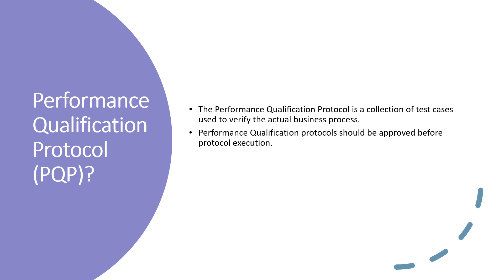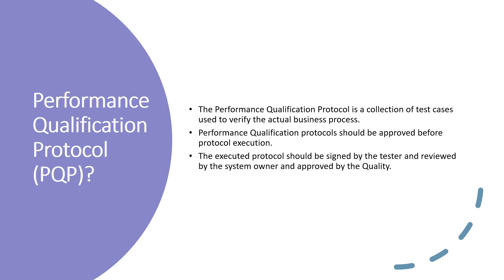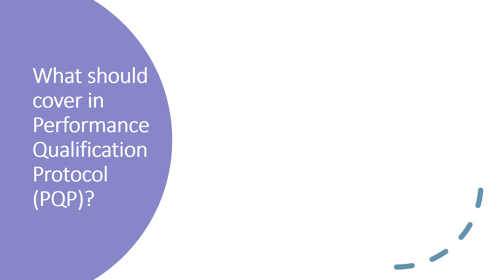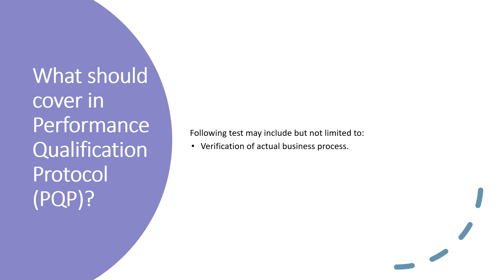Also, operational qualification must be executed and approved prior to starting the performance qualification. The executed protocol should be signed by the tester, reviewed by the system owner, and approved by the quality. The performance qualification should check the performance of the system with respect to the actual process — that is the process used for routine activity. The following tests may be included, but not limited to: verification of actual business processes.